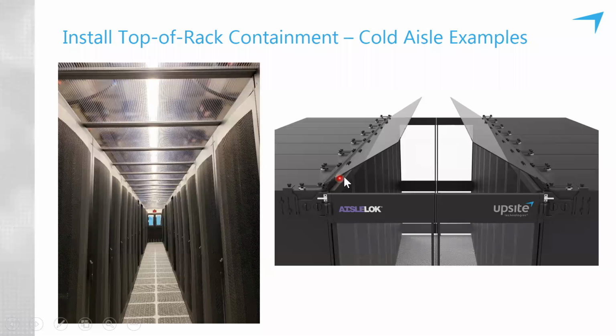And on the right here, we see examples of the Upsite AisleLok rack top baffles, and these angled baffles are intended for cold aisles. The angle is fixed, it doesn't move, it's not adjustable, and it's not tied to the fire suppression system. The opening is what allows this to be approved by fire marshals. Leaving it partially open prevents it from obstructing gaseous fire suppression, which can obviously get in.